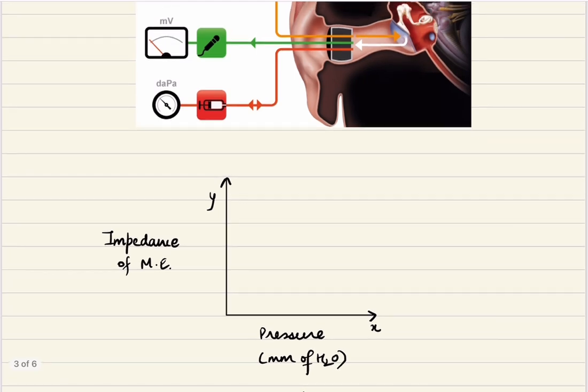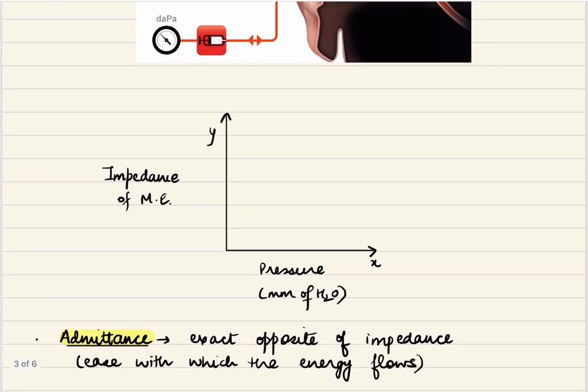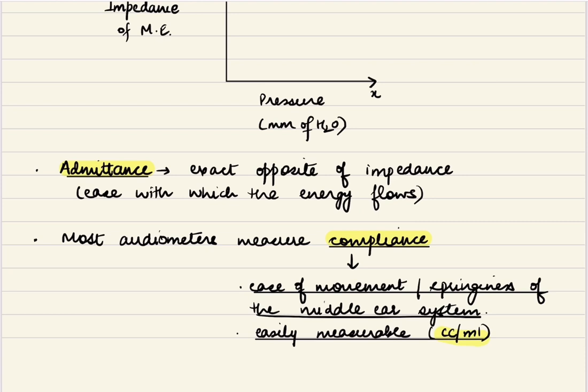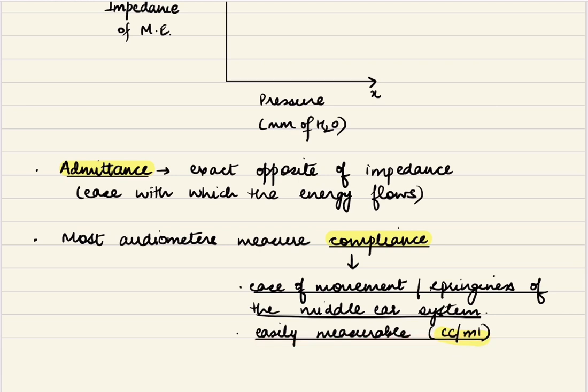However, it is easier to measure the admittance of the middle ear. Admittance means the exact opposite of impedance — impedance means resistance to flow, and admittance means ease with which energy flows. It is even easier to measure the compliance of the middle ear. Admittance is indirectly measured through compliance, and compliance is the ease of movement or springiness of the middle ear system. This is easily measurable in milliliters, and most audiometers now measure compliance in milliliters.